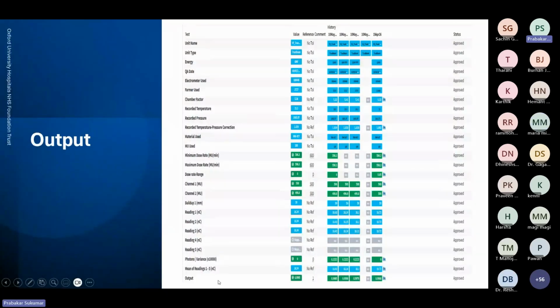So you are creating a test list by adding a test to each one, and then you can assign the test list to different machines. You don't want to create a different test list for different machines. You are creating one test list and then assigning it to different machines, so it is not replicating. If you are creating a new machine, you will not be doing a new test list; it is just one test list. You can just assign it to the different machines. That is really helpful, that you're not copying and redoing things.